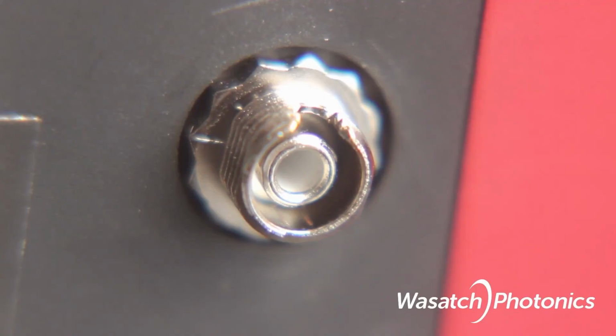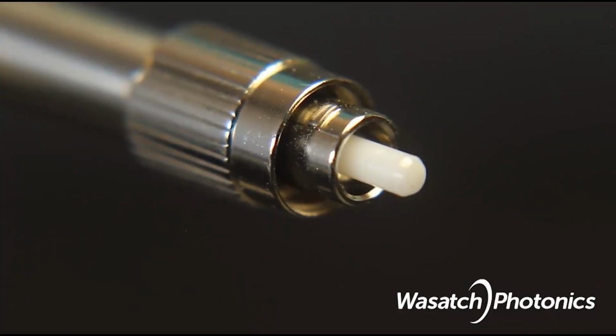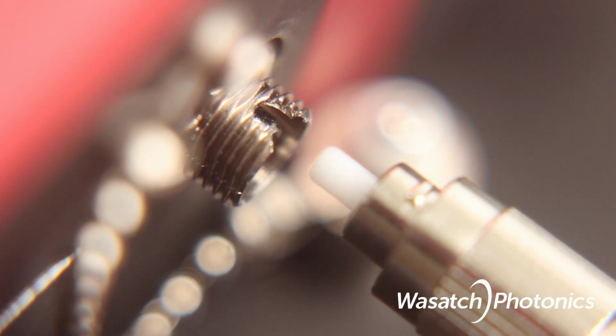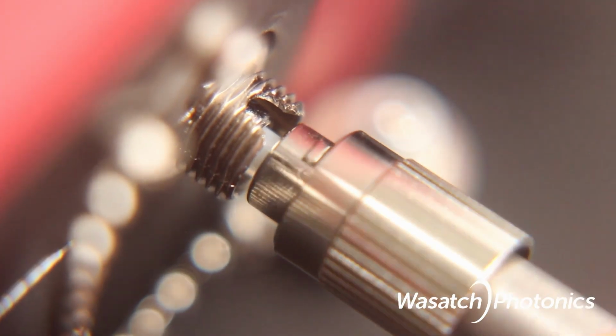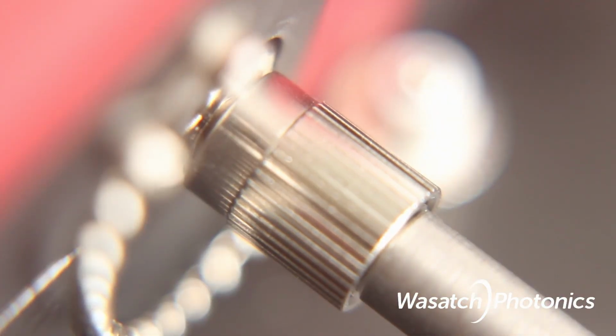For the laser, you'll need a so-called FC-PC fiber, which has a ceramic tip and a bigger connector. The FC plug can only fit into the connector in a certain orientation. The fiber has a little stub. This stub needs to be rotated to line up with a little notch on the laser end. Rotate the fiber to the correct orientation. It should slide in easily, then finger tighten the screw.